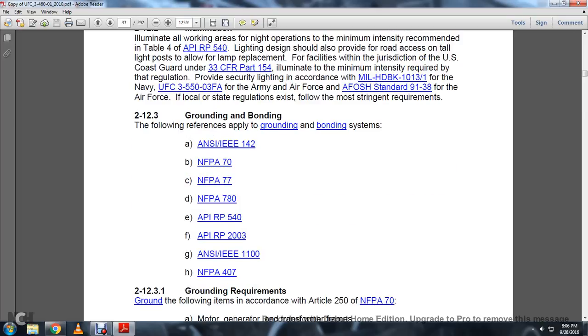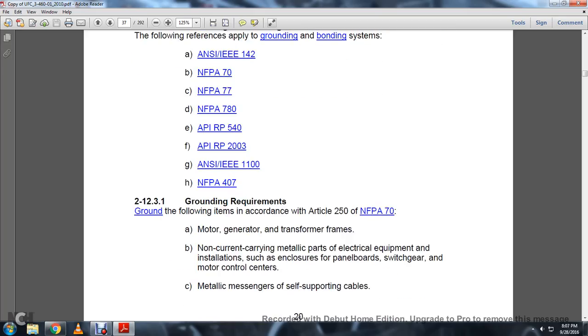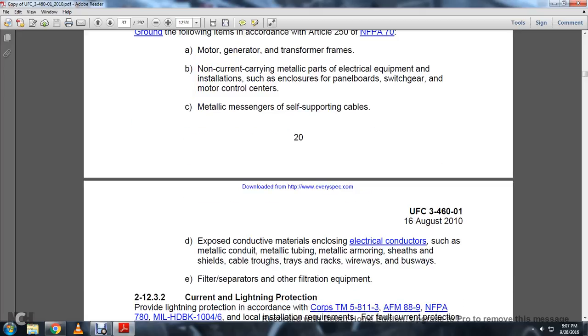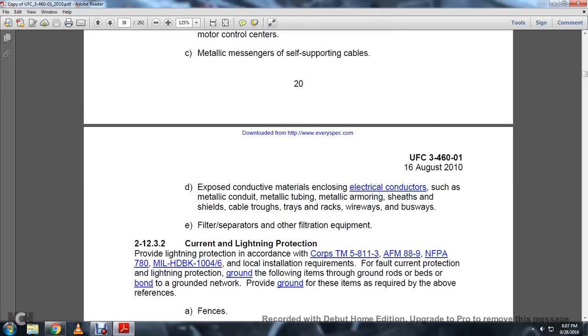Alright, grounding and bonding. The following references apply to grounding and bonding systems: ANSI/IEEE 142, NFPA 70, 77, 780, API RP 540, API RP 2003, ANSI/IEEE 1100, NFPA 407. 212.3.1 Grounding requirements. Ground the following items in accordance with Article 250 of NFPA 70: motor generator transformer frames; non-current-carrying metallic parts of the electrical equipment of the installation, such as enclosures, panel boards, switchgear, and motor control centers; and metallic messenger self-supporting cables. Exposed conductive materials associated with electrical conductors include metallic conduit, metallic tubing, metallic armoring, sheaths, shields, cable troughs, trays, racks, wireways, busways, filter separators, and other filter equipment.